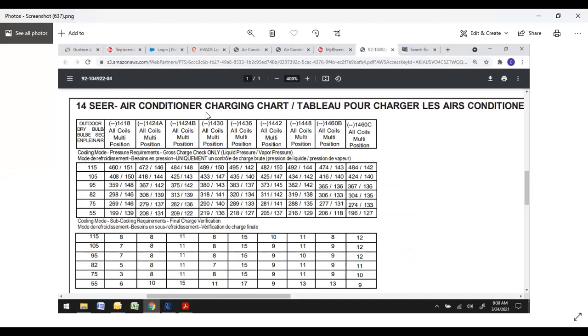So here's your typical charging chart. I picked a 14 SEER air conditioner. So we'll take a 3 ton. If you go to the 1436, you'll see here it says all coils, multi-position. That means it doesn't really matter what coil or what orientation your furnace is in, you can use this chart. Other charts will tell you upflow, or give you specific coils. It may say one coil, upflow, downflow, horizontal, right or left. That's where it's important to understand what your furnace orientation is if it calls for that. In this case here, it doesn't matter. So we'll come down here, 1436. We'll go to 82 degrees.